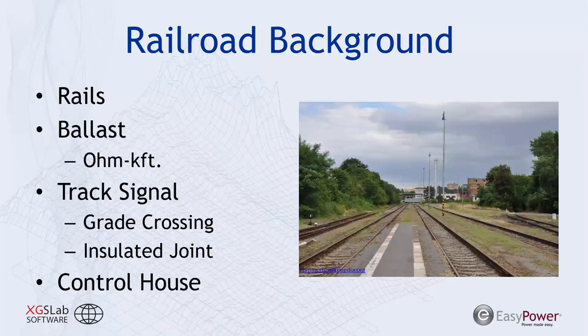And much of that track signaling system is placed into control houses, and not every single piece of equipment may be located in the control house, but many of them are co-located in central locations like the control house. These houses help protect it from the environment. They often do have a ground ring around them that can help with the concerns we're talking about with AC interference, but it's possible that ground ring is insufficient for the type of induction or capacitive or conductive coupling that you could see from AC interference or the effects of a transmission line next to a railroad.